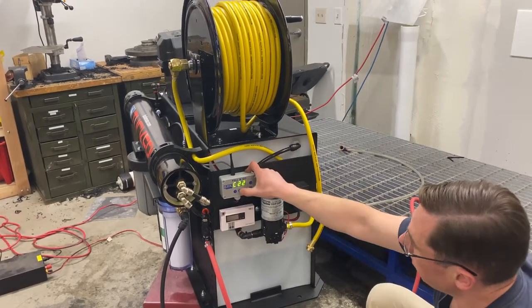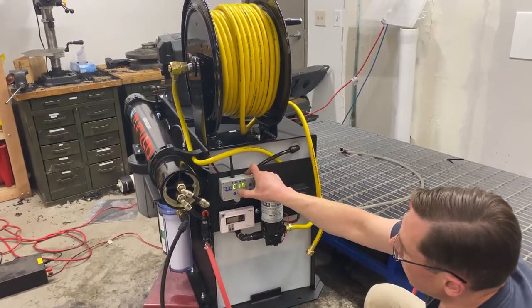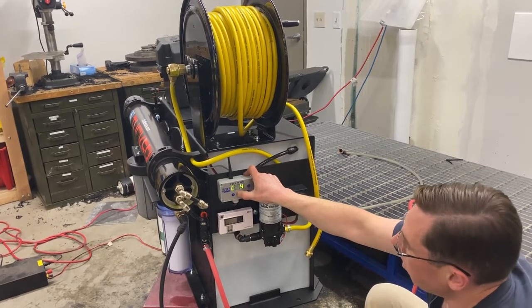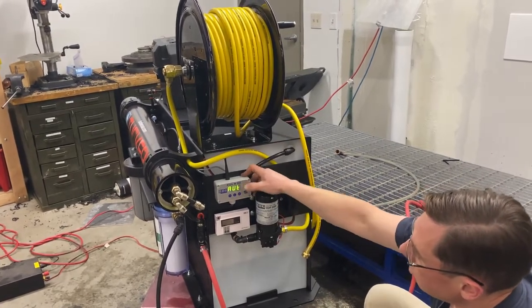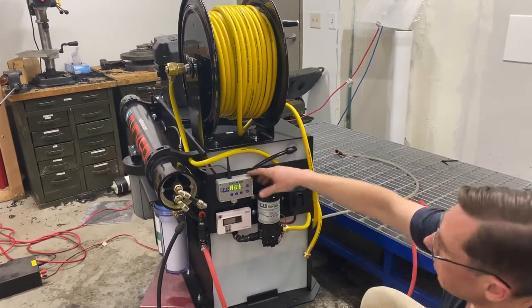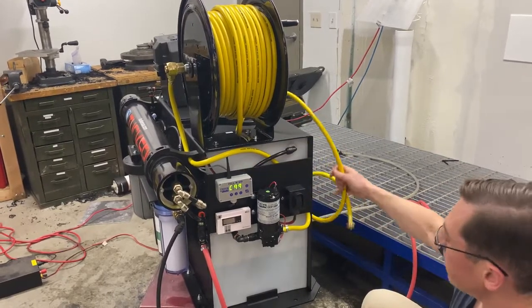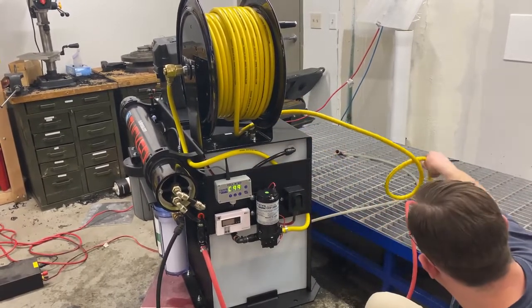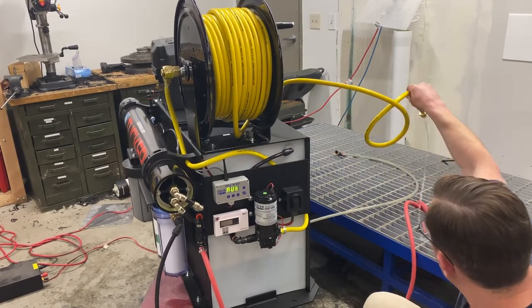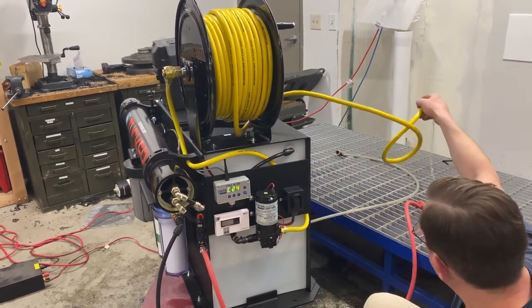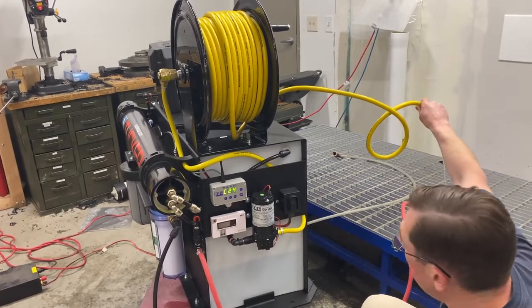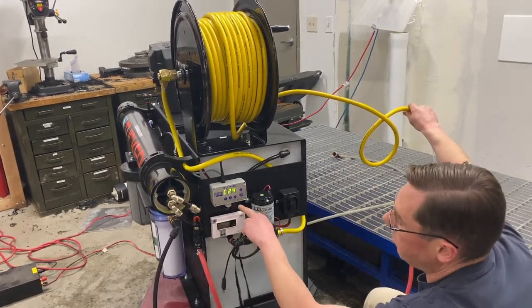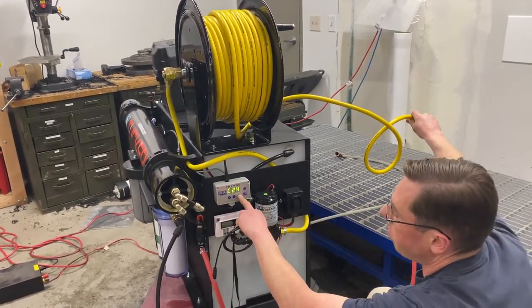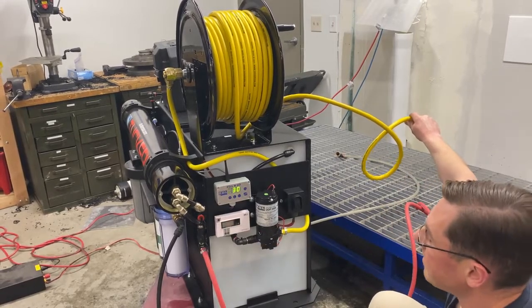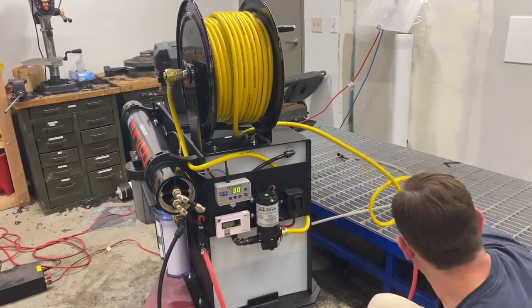It's too sensitive. So I'm going to go all the way down past cal 0 to AUT, automatic calibration. You press enter. It's going to flash C99. And now the pump is running kind of no matter what. And you see it's moving water. So it just needed to be a little less sensitive. C24, press enter, it's set.